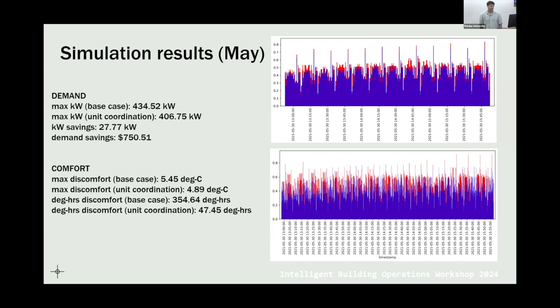Some of the lessons we learned from practical application had to do with using smart thermostats to control the rooftop units. There's often a delay, and that delay affects how you model the thermal zones, because you may need to offset the changes in building temperature by one time step to get an accurate model of the cooling load's influence on the thermal zone.